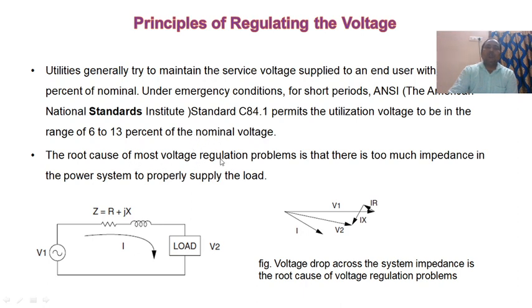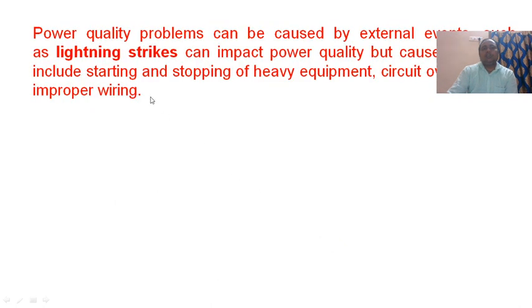The root cause of most voltage regulation problems is that there is too much impedance in the power system to properly supply the load. Here please see, there is a source, there is an impedance, there is a load. So the current travels from source to load. Because of the impedance, there is a drop. The voltage drop across the system impedance is the root cause of voltage regulation problems. So here there are two drops, resistive drop and reactive drop. Current always lags because all the loads are inductive in nature. Power quality problems can be caused by external events such as lightning strikes, as already discussed.